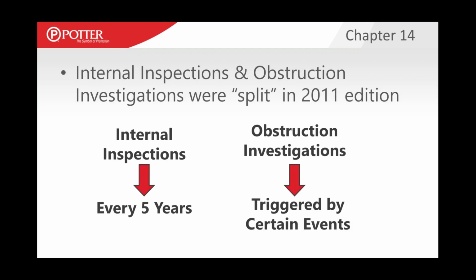Let's call it an internal inspection to start with. We'll explain what changed here in a minute, but internal inspection and obstruction investigations used to all be lumped together in Chapter 14 of NFPA 25. In the 2011 edition, these 2 tasks were split into 2 sections of Chapter 14. Internal inspection, looking inside the pipe, is a frequency-based task. It has to occur every 5 years, period. It occurs every 5 years, regardless.